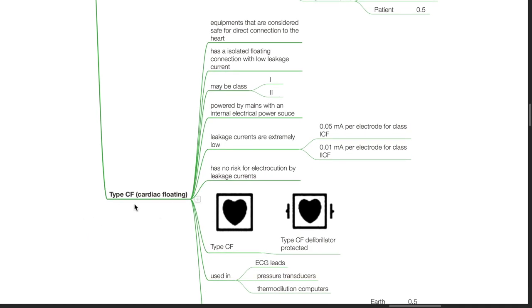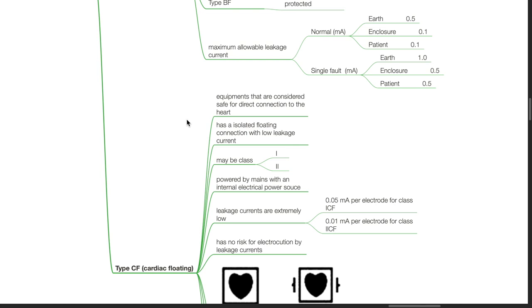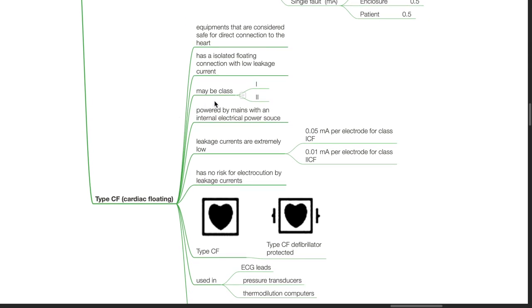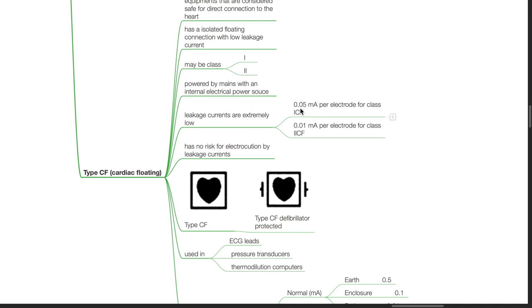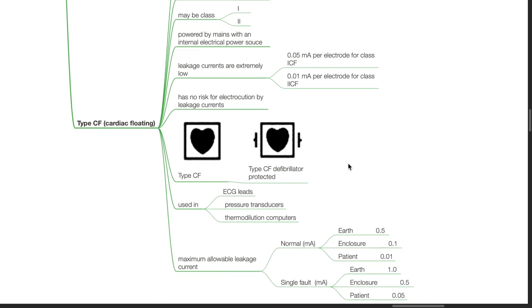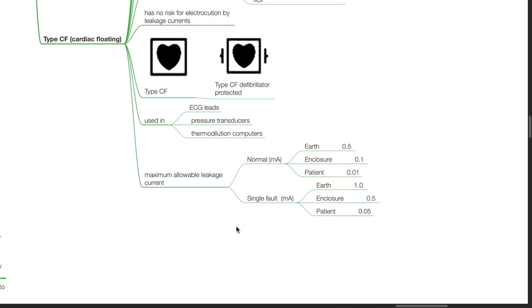Type CF or cardiac floating equipment are considered safe for direct connection to the heart. They have an isolated floating connection with low leakage current, may be either class 1 or 2, and are powered by mains with an internal electrical power source. Leakage currents are extremely low: 0.05 milliamps per electrode for class 1 CF and 0.01 milliamps per electrode for class 2 CF. There is no risk for electrocution by leakage currents. These equipments are used in ECG leads, pressure transducers, and thermodilution computers. Maximum allowable leakage current during normal conditions: Earth 0.5, enclosure 0.1, patient 0.01 milliamps. During single fault: Earth 1, enclosure 0.5, patient 0.05 milliamps.